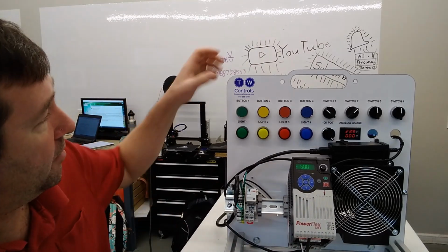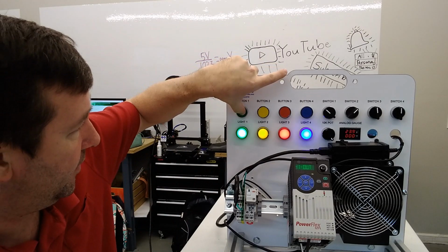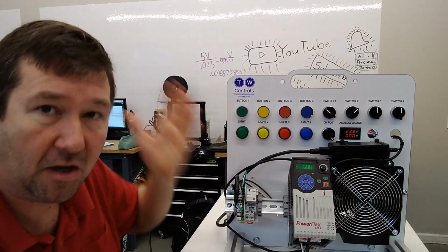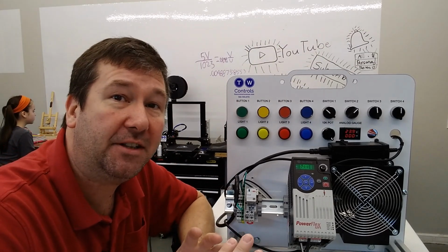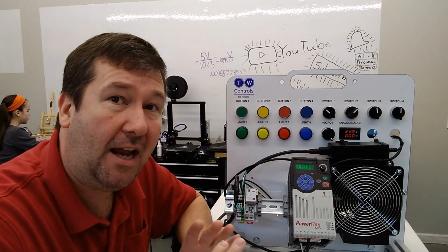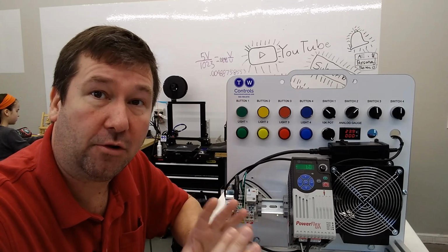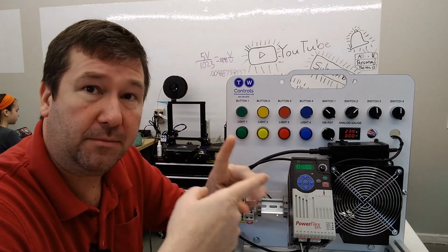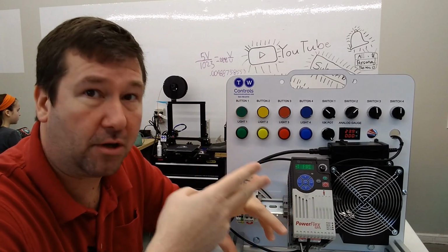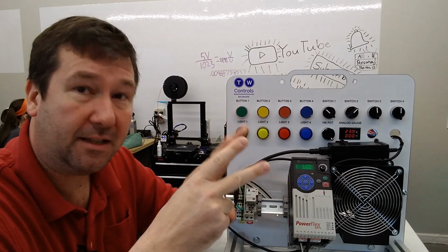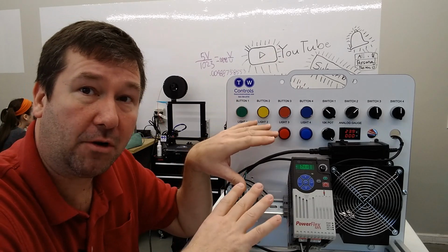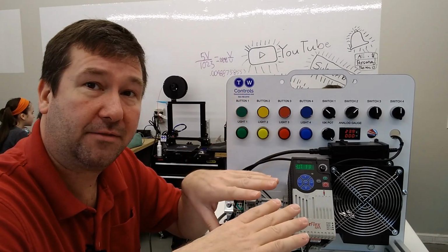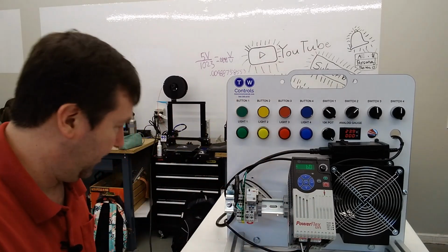Okay, so we've downloaded our program and we press the green button. All of our outputs come on. We press the red button, all of them go out. It works exactly the same. The difference is now these outputs, or mainly the local variables, are going to be retentive. Which, first, if you're converting a program from, say, a Micrologix PLC or a Controllogix PLC, then this is how they would actually work, because outputs are retentive on RSLogix 500 and in Studio 5000.